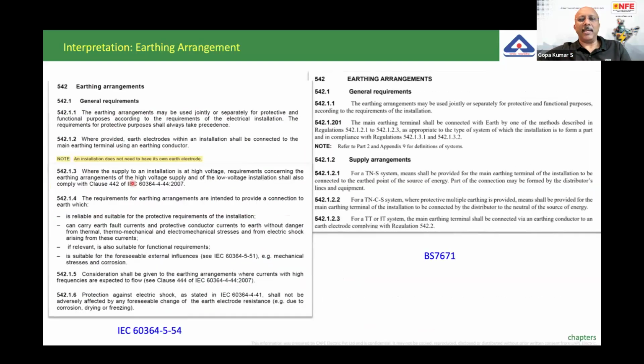Now another interesting subject, 542 earthing arrangement. So here there is 542.1.2, where provided, earth electrodes of an installation shall be connected to the main earthing terminal using an earthing conductor, and then there is a note, 2011 version I am reading: an installation does not need to have its own earth electrode. So the subject is very clear, whereas when you come to BS 7671, 542.1.2 supply arrangement. Now here what they say is, for a TN-S system, means shall be provided for the main earthing terminal of the installation to be connected to the earthed point of the source of energy. Part of the connection may be formed by the distributor's line and equipment.